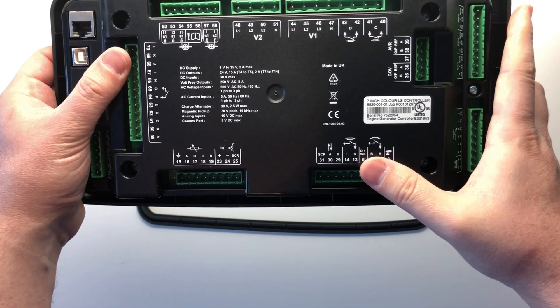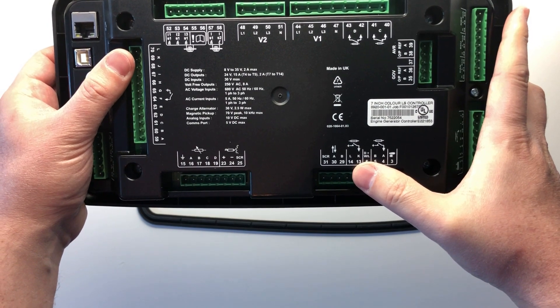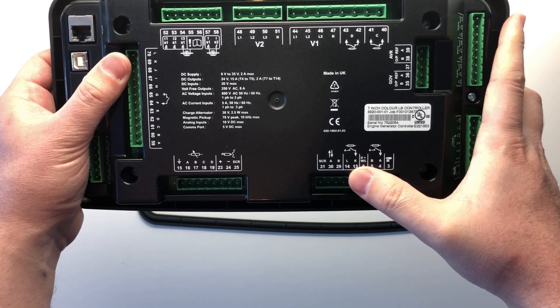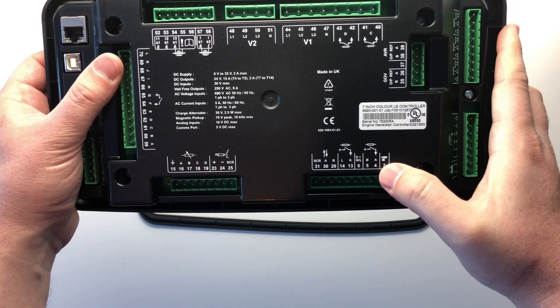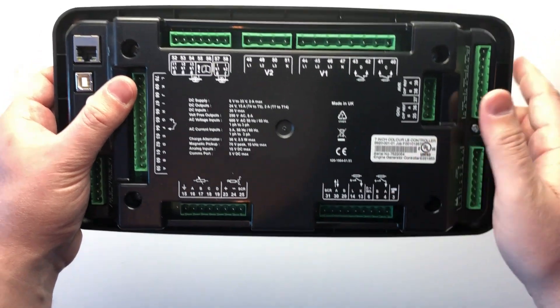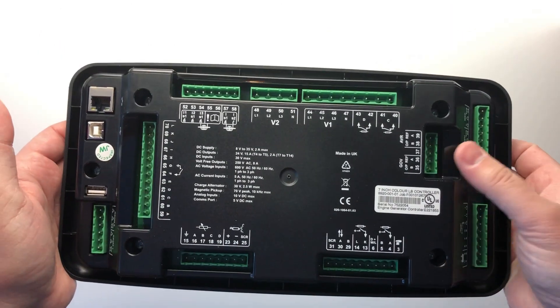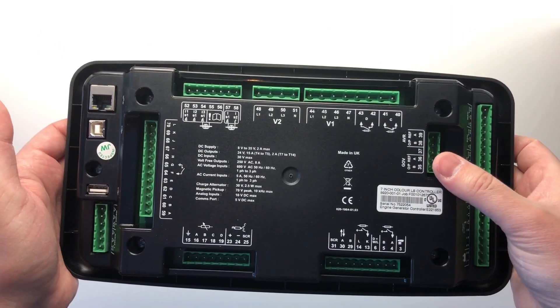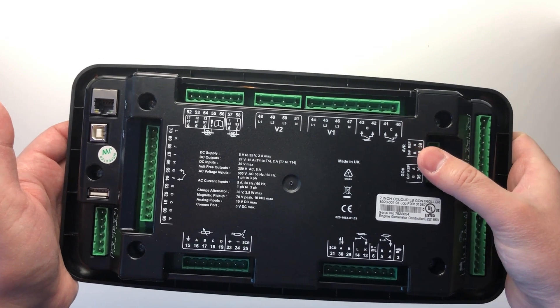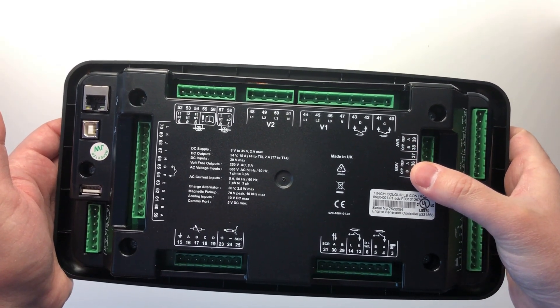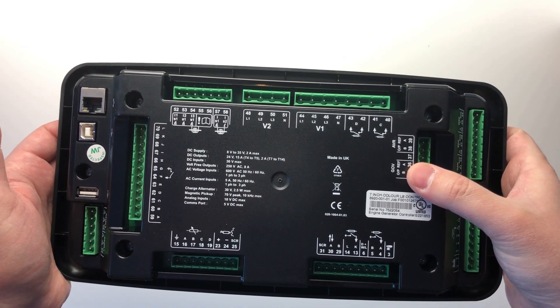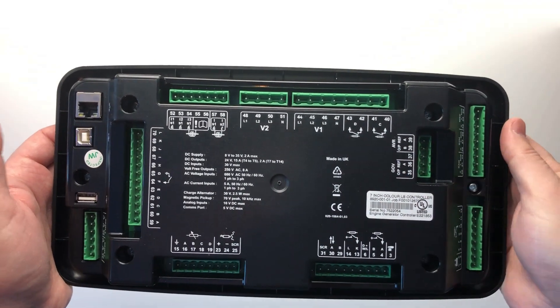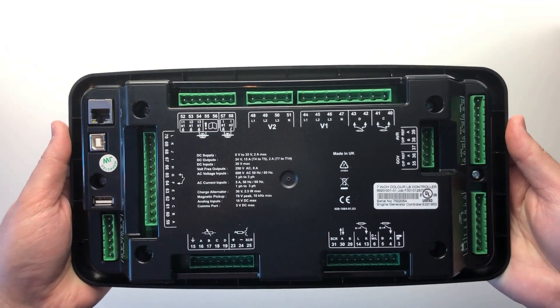We then have the two volt-free outputs for fuel and crank, the D plus excitation or WL terminal on some charge alternators, and the emergency stop. The DSE8920 has built-in AVR and governor outputs. These have a range of minus 10 volts to plus 10 volts for controlling any type of AVR or governor when synchronizing and load sharing.